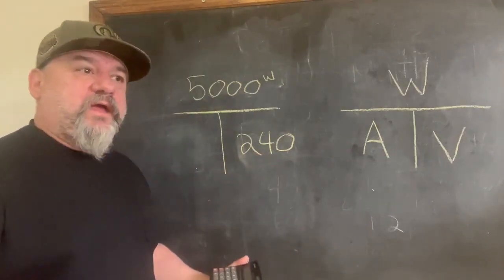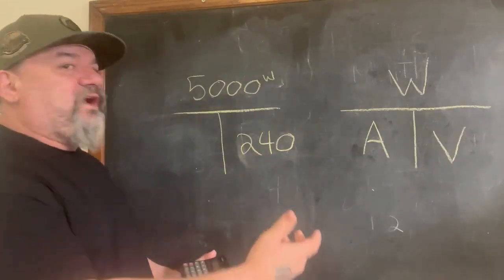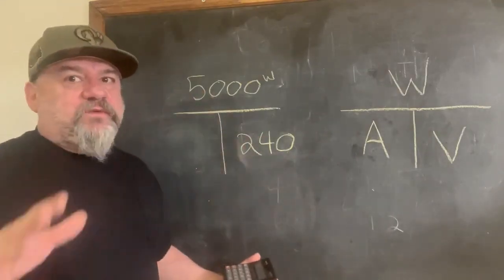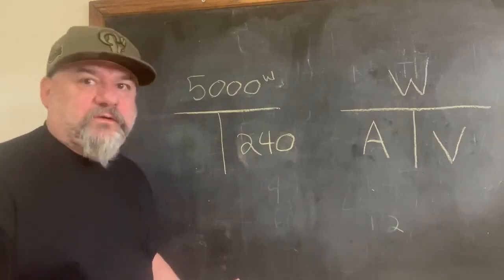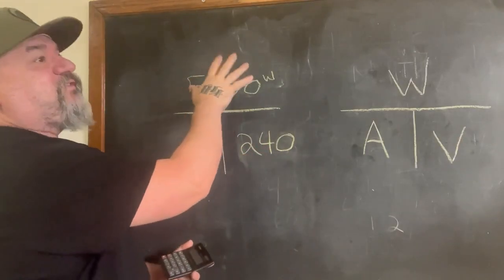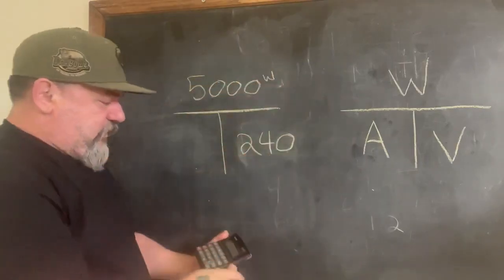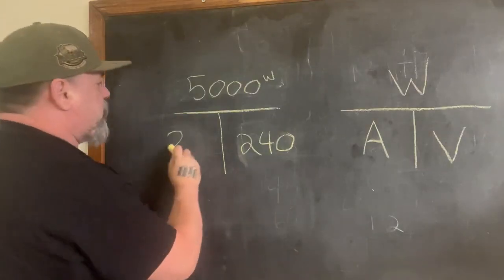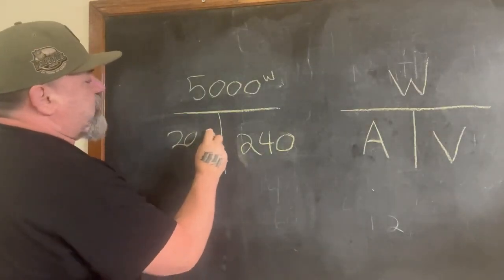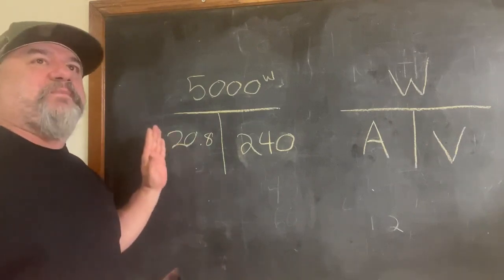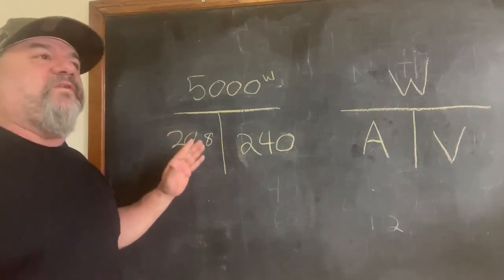We got 240 volts. We know it's the 220 plug, or 240 volts, what we use in the industry, and a 5000 watt welder. 5000 divided by 240 is 20.8 amps. So we'll call that 21. So that's going to be a 30 amp breaker because we're over.